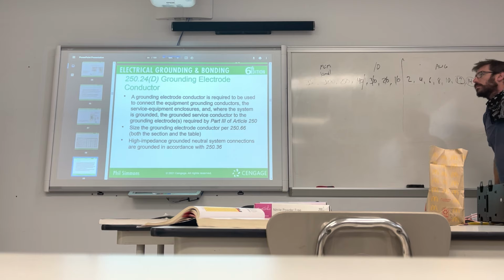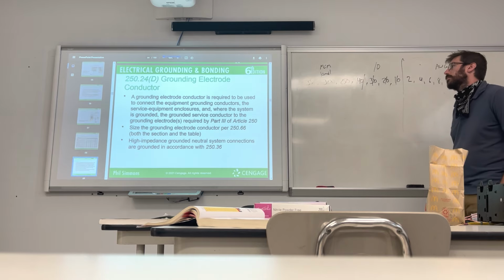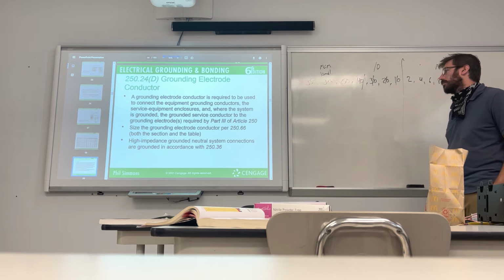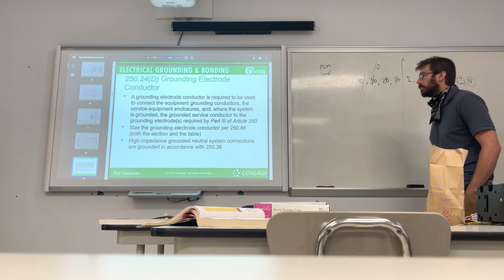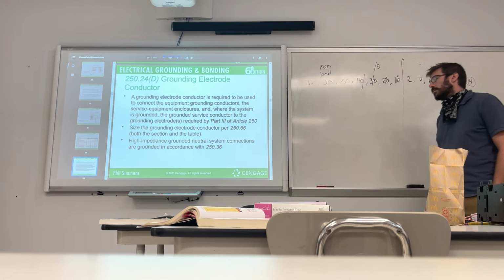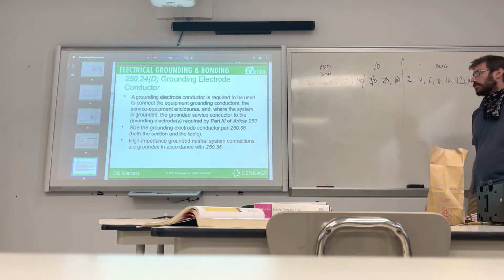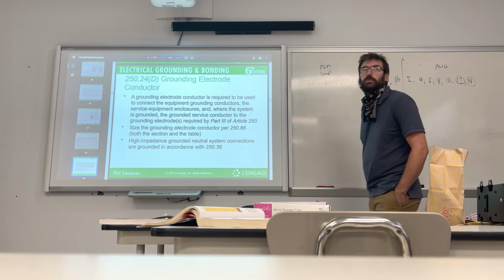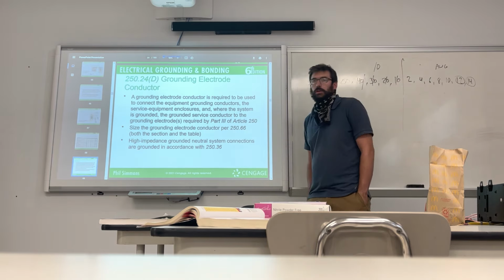Grounding electrode conductor. A grounding electrode conductor is required to be used to connect the equipment grounding conductors, the service equipment enclosures, and, where the system is grounded, the grounded system conductor to the grounding electrodes required by Part 3 of Article 250. Size the grounding electrode conductor per 250, both the section and the table. High impedance grounded neutral system connections are grounded in accordance with 250. All this means is that one ground rod or one grounding electrode does not fit all.